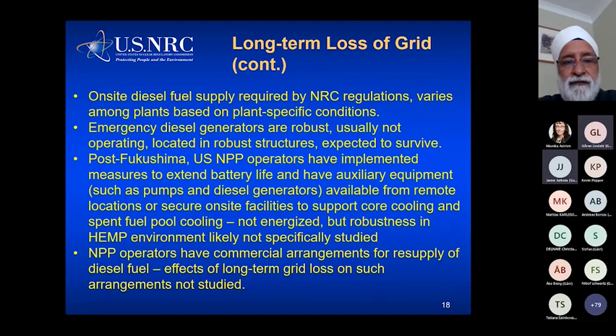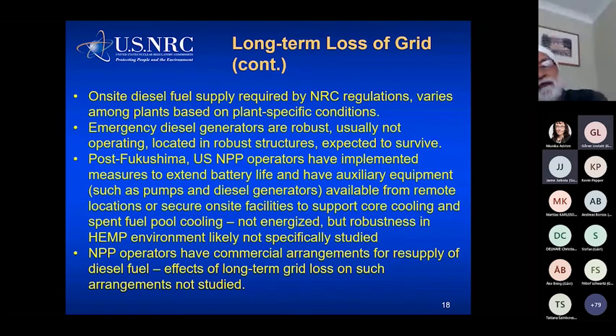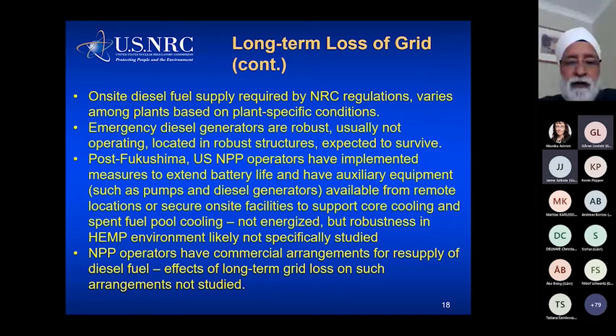We have some on-site fuel oil for the diesels, and we know it's limited. We also know that diesel generators are robust. They are not usually operating, and we expect them to survive during an EMP event. Post Fukushima, we've installed auxiliary equipment. We've managed to extend the battery life. We've got other pumps and diesel generators. Some of them are portable that we can secure from remote locations and help safe shutdown of the plant if needed. And we also have, in the US at least, almost all operators have commercial arrangements for resupply of diesel fuel oil if and when needed.